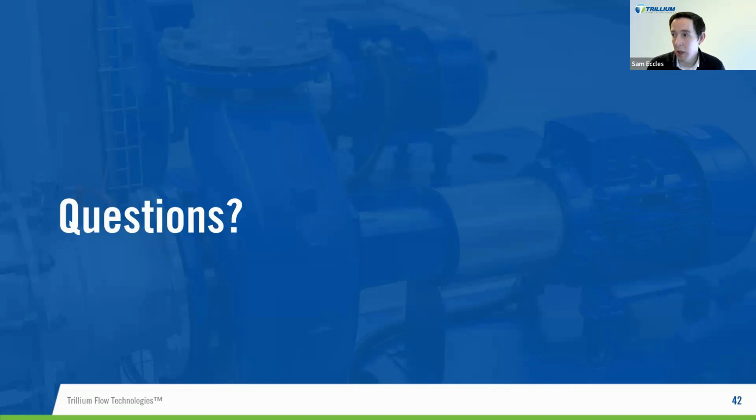There will also be limits from the pump side, and that's less critical on small single stage units, but as you get into flexible rotor multi-stage pumps, this becomes very significant. And we could talk to you for another 2 hours till you fell asleep about lockout zones and resonance ranges that you will run into. There's also an element of support that the pump needs to operate well, and at very low speeds that just doesn't happen. So yes, there are minimum speeds that we need to enforce, and sometimes that's governed by the pump vendor, sometimes by the motor and VFD supplier.